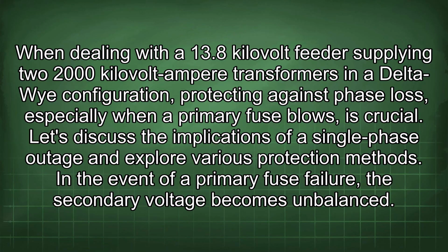When dealing with a 13.8 kV feeder supplying two 2000 kVA transformers in a Delta-Wye configuration, protecting against phase loss, especially when a primary fuse blows, is crucial. Let's discuss the implications of a single phase outage and explore various protection methods. In the event of a primary fuse failure, the secondary voltage becomes unbalanced.